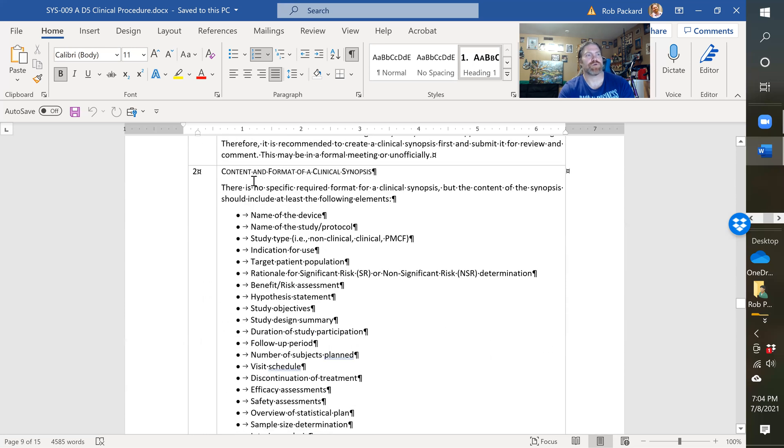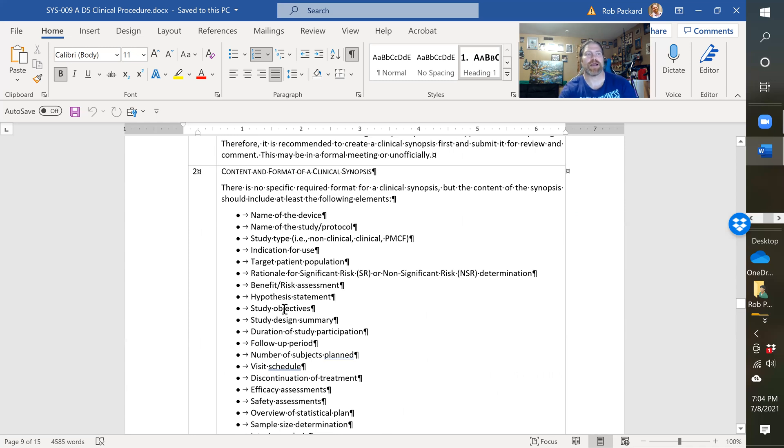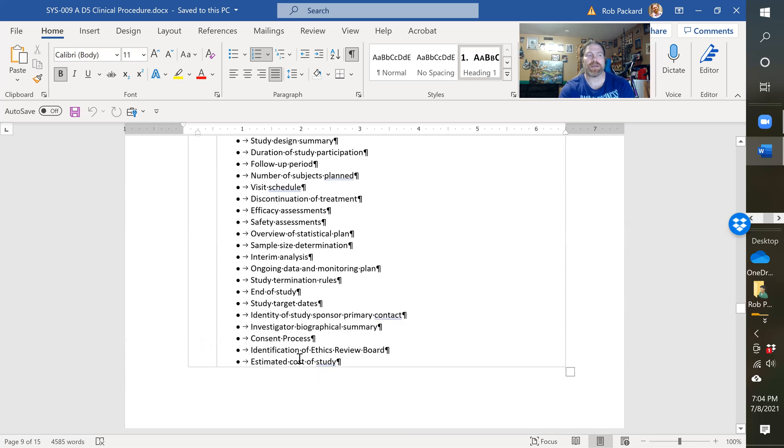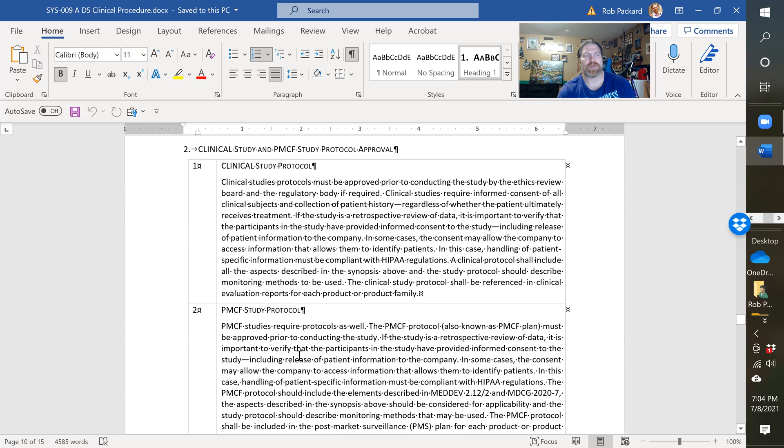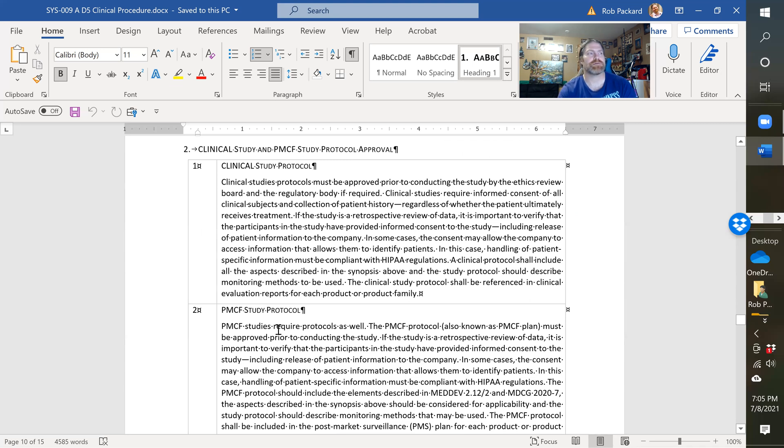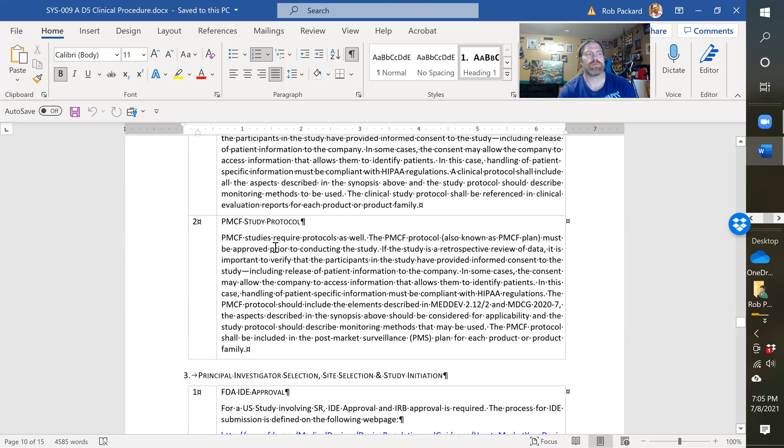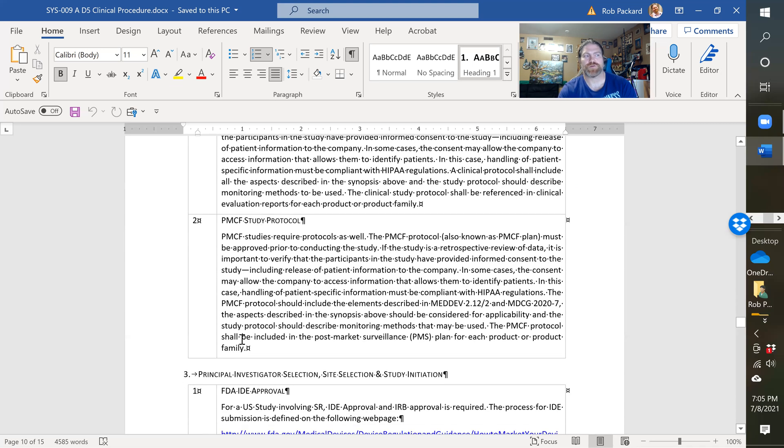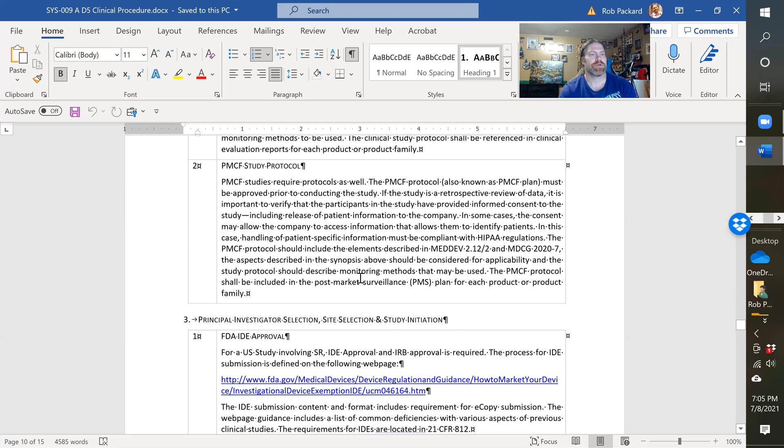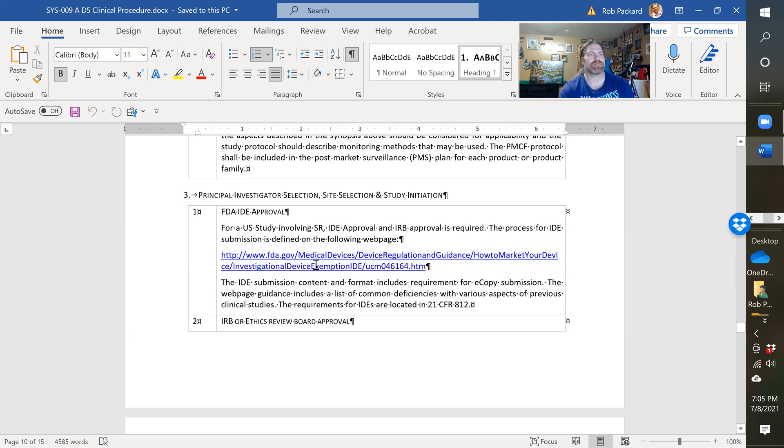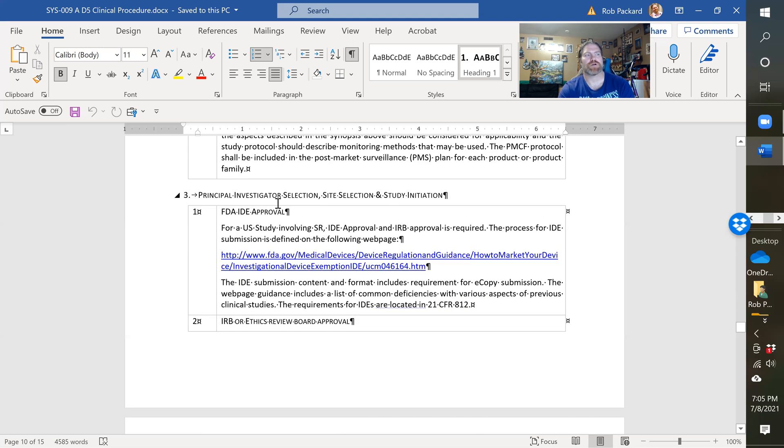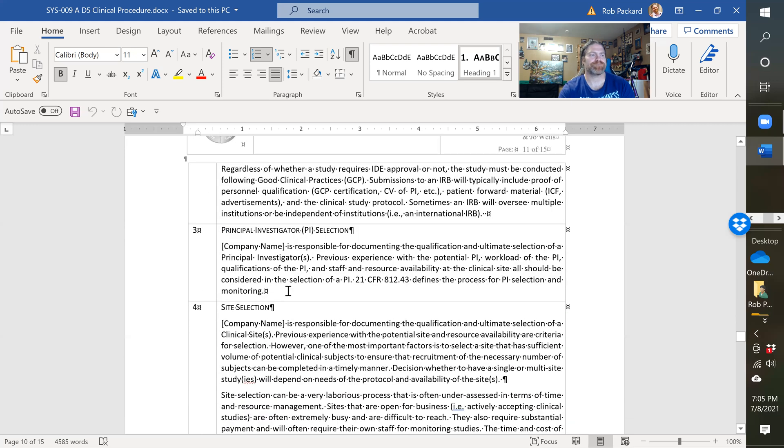We go step-by-step through what the procedure does. Here we have content that should be in a clinical synopsis - before you would even create the protocol, you might create a synopsis. This is like an outline of what would be in your clinical study. Then we have the protocol. We also address post-market clinical follow-up (PMCF) studies here as well, and it references the EU guidance and MDCG guidance. It talks about investigator selection, site selection, and study initiation.